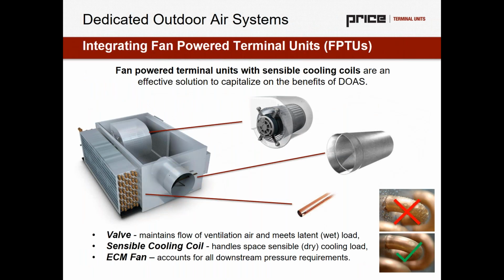So when I say it really is a chilled beam performance type unit in a fan powered series layout, it is true. And we can see this on screen broken out a little more clearly. We have that primary air inlet, that primary air valve, which is maintaining the flow of ventilation air and meeting our latent load within the zone. We have that sensible cooling coil, which for all intents and purposes is a chilled beam strapped to the side of our unit, handling the space sensible cooling load. And then we have that ECM fan, the electronically commutated motor, which is very high efficiency and can provide quite a bit of airflow below the Washington State Energy Code 0.12 watts per CFM requirement. It's also accounting for the downstream pressure requirements of the ductwork, the air pressure drop of the coil, perhaps the air pressure drop of an acoustical silencer or something of that nature as well.